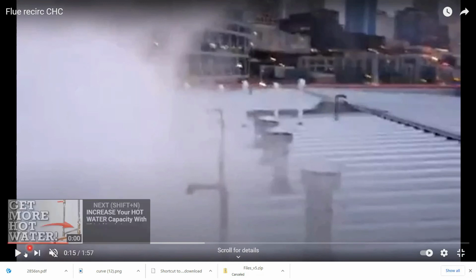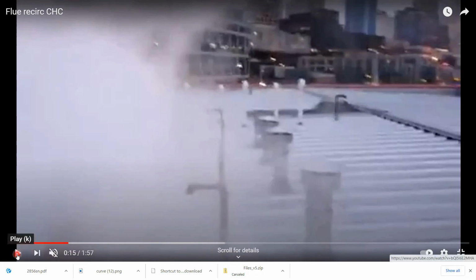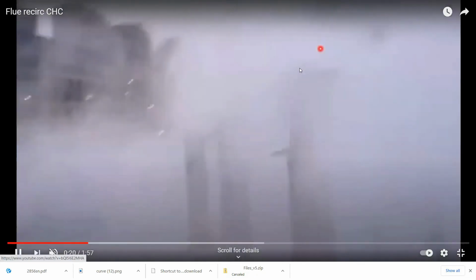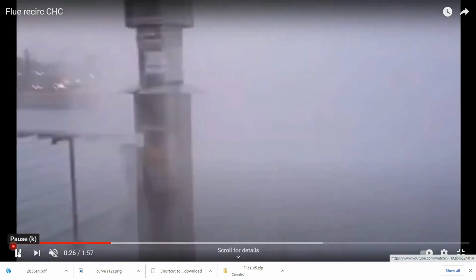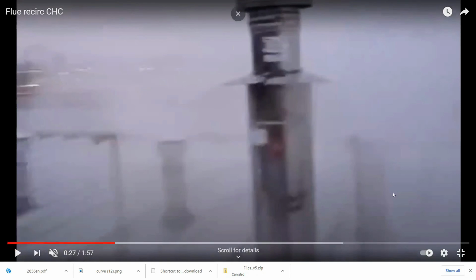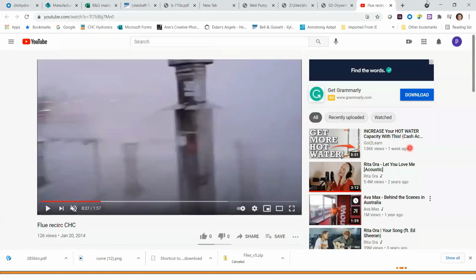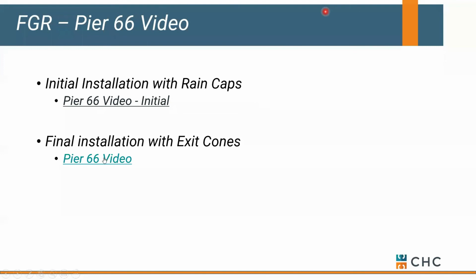So what's happening is the flue products are trying to get out of the building, but they're hitting resistance here on the rain caps, okay, the top of the caps, and we kind of have a cold air inversion that's forcing those flue products down towards the roof of the building. That's creating flue gas recirc. That creates a lot of challenges for us, and the boilers tend not to like that.